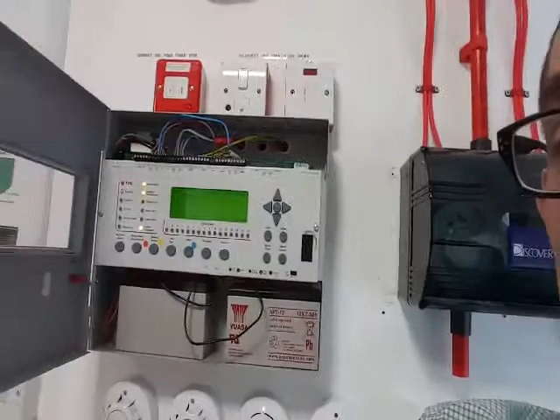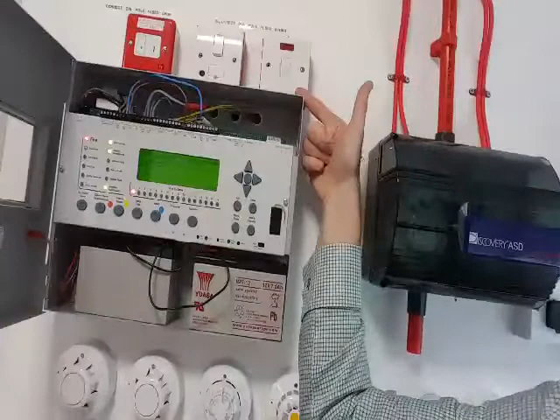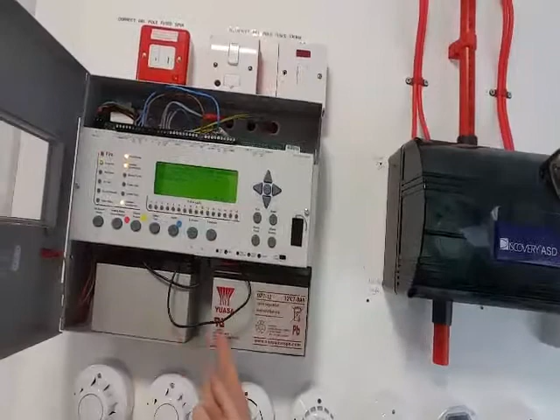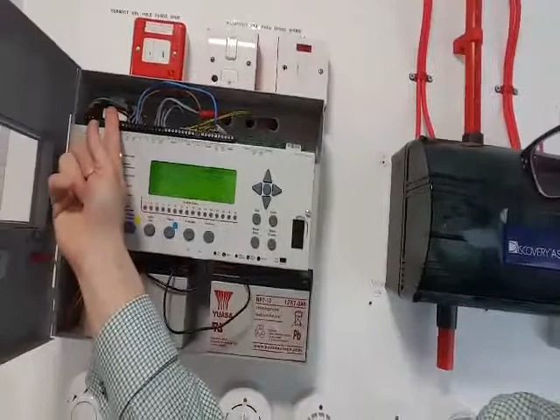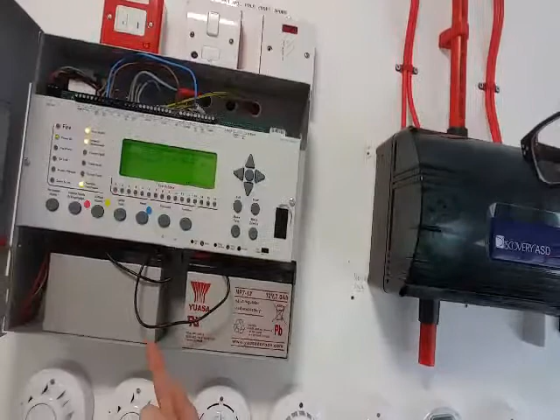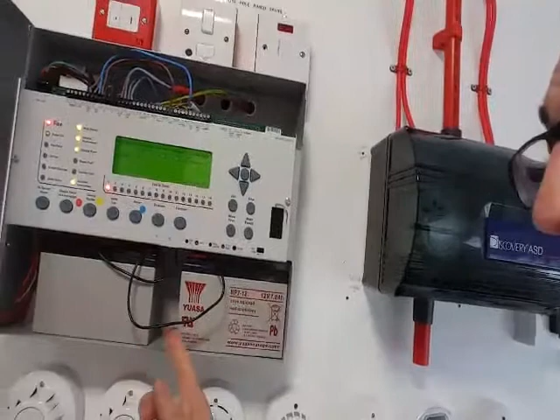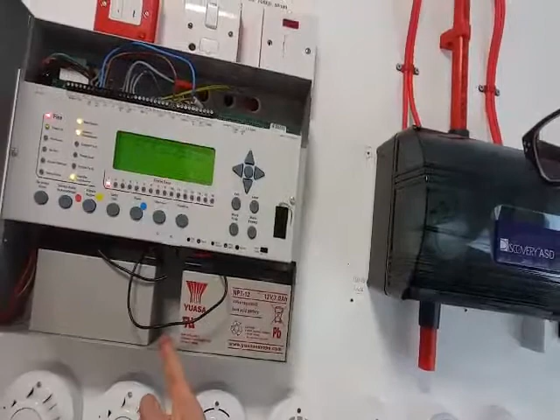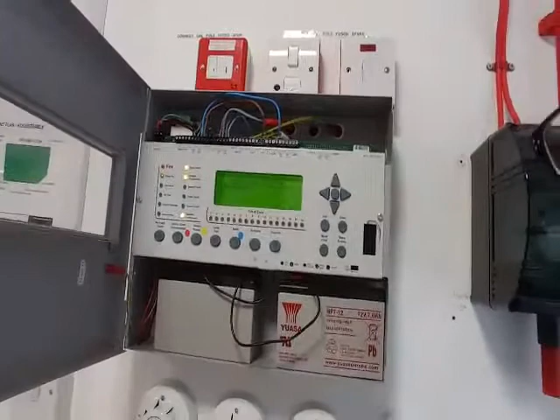We're now going to talk about B. B, on fire alarm systems, is for batteries. All fire alarm systems have two forms of supply. They have the mains incoming supply, which is 230 volts, and they have standby batteries. These are rechargeable via the mains supply, and they give a minimum of 24 hours of additional power to the fire alarm system. They're quite large and normally 12 volts, starting at around 2 amps, but they can go to 16 amps or even 24 amps, which is the size of a car battery. So B in this context is for batteries.